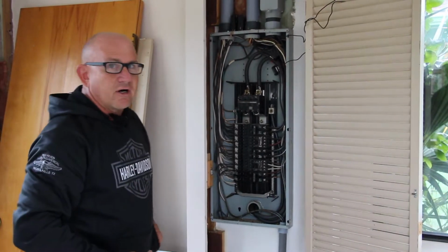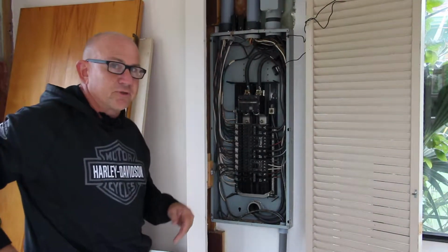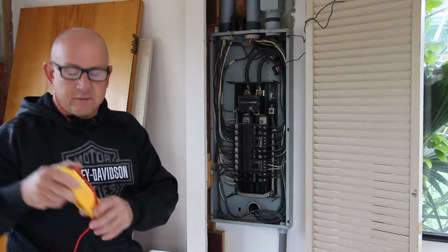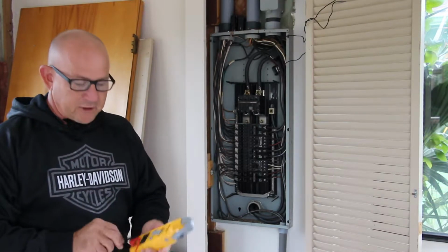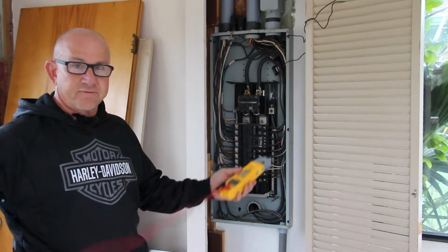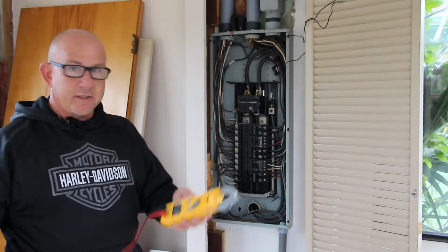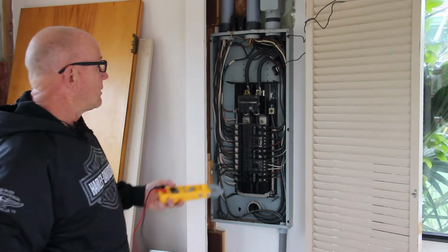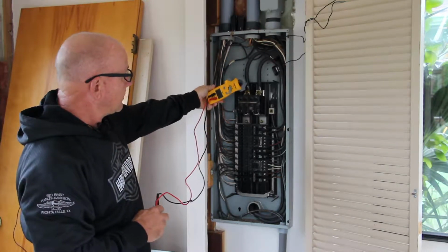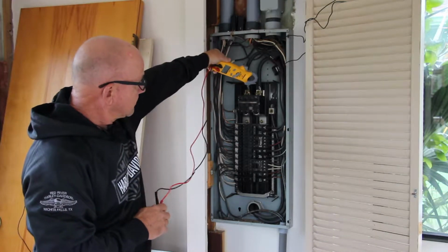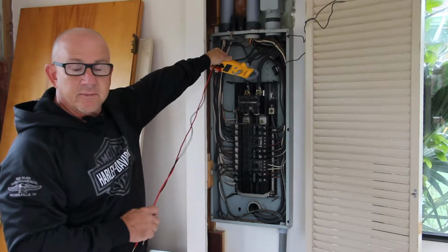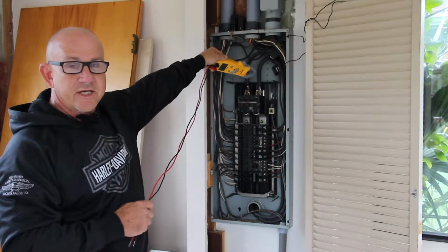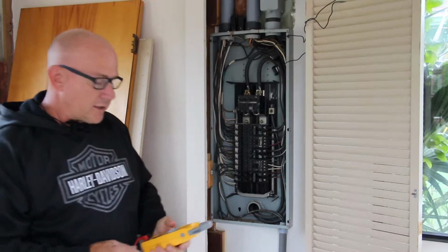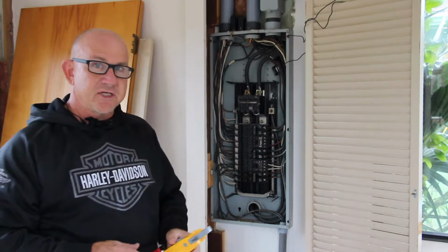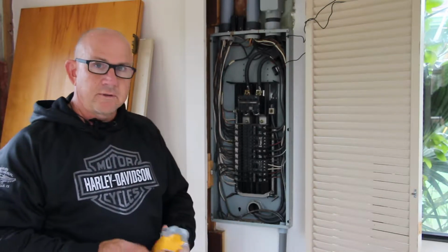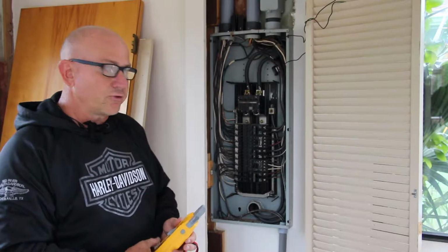Once we get the cover off, the next thing we want to do is find out if there's power on the actual conductors coming into the service panel. So again, I'm going to get my non-contact voltage meter out here, and I'm going to check right up here, and we can see that it's showing us that the power is on. So we have to understand that the electricity is hot and it could be dangerous, and we need to be safe and cautious of what we're doing.